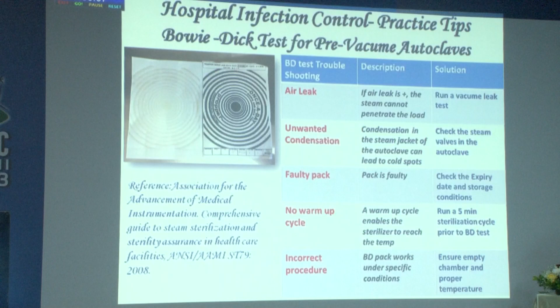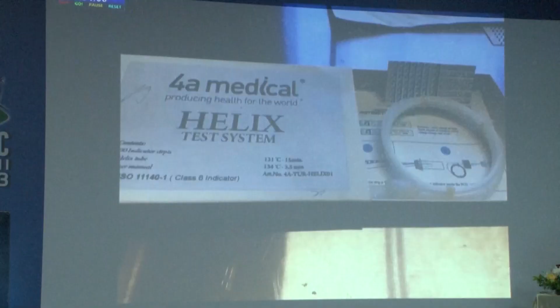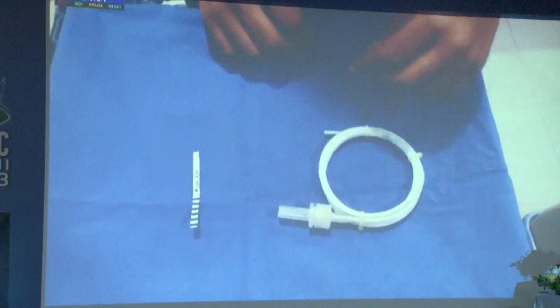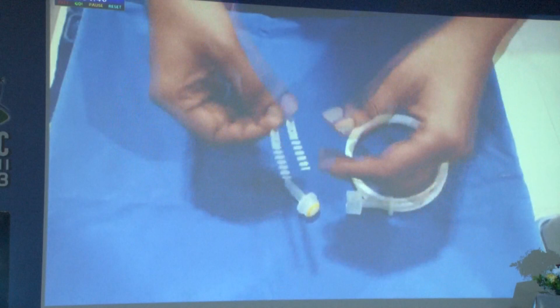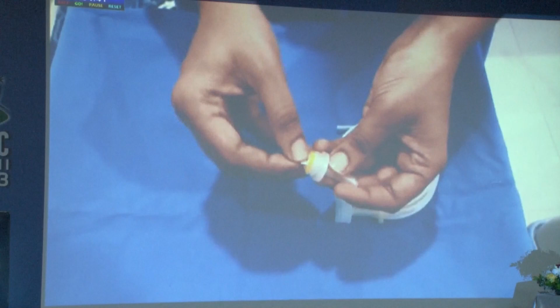This tells you the troubleshooting of a failed Bowie-Dick test. The common things are air leak, unwanted condensation, faulty pack. Sometimes a warm-up cycle is needed in certain autoclaves, and an incorrect procedure. You need to educate your staff of what has to be done in the event of a failure. The Class 6 works well when you're doing hollow instruments. This basically ensures your air is removed from the hollow tubings. It consists of a 1 meter long tube with a 0.1 millimeter lumen with a case at one end. The way you fold your strip is very important. Fold it inwards and not outwards. And then it is placed inside this casing, which is then fixed to the tube.